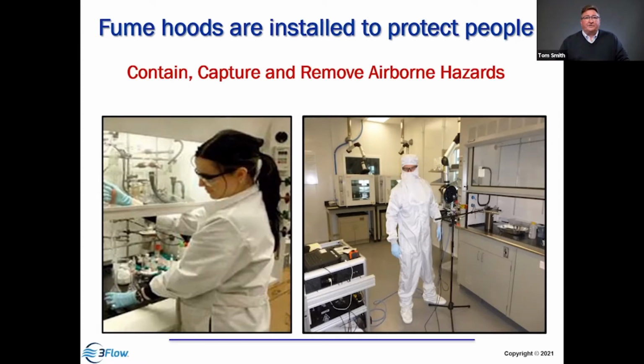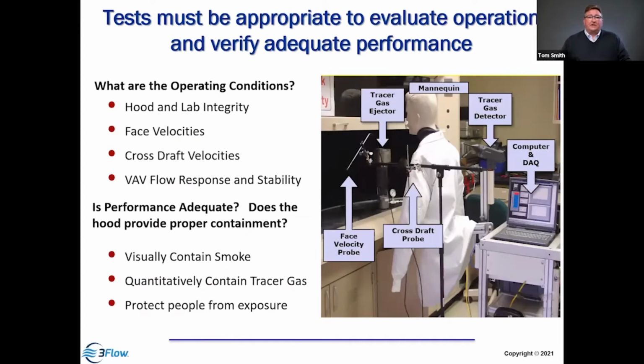And so we want to make sure that it has the ability to contain materials, to capture those materials, and remove them from the hood in the building. And that's our job, and that's the purpose of this training course, to make sure that they're effective in achieving this objective. So we're going to test it. We've got an ASHRAE 110 test that we're going to go through in detail today and tomorrow. We're going to talk about the operational conditions. How do we evaluate the conditions under which the hood's operating?